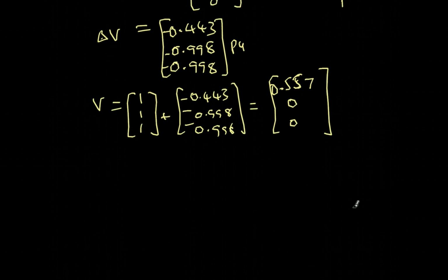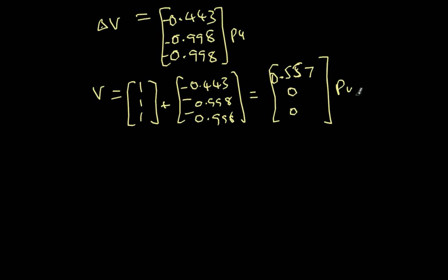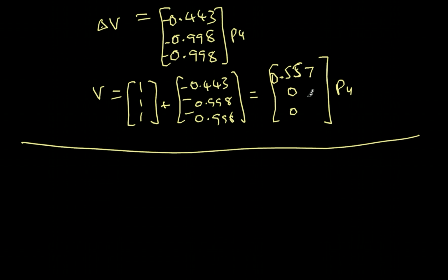So for the earlier fault, the voltage went from 1 per unit to 0.81 per unit, whereas here you see the bus 1 voltage is reducing even further because the fault has moved close to the generator. And you notice that bus 3 and bus 2 both are 0 volts because the fault is at bus 2, and at bus 3 there is no load, so both are at 0 volts.